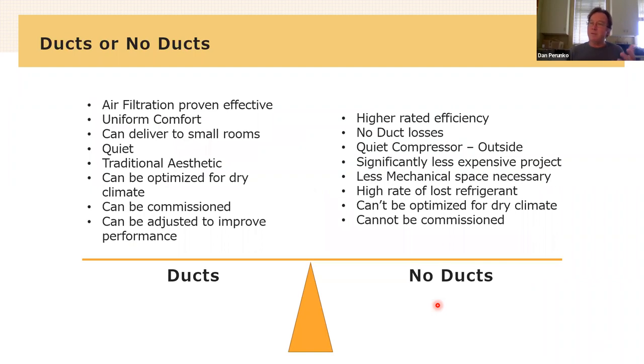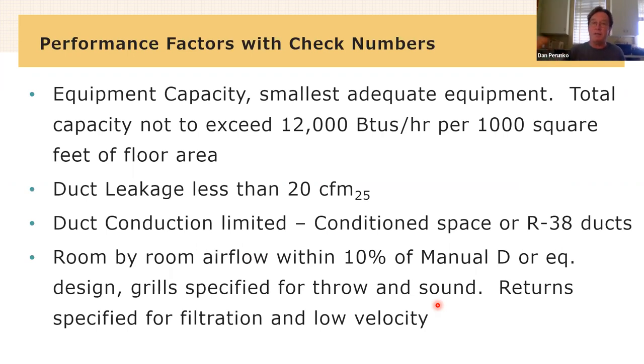And you have to decide whether you're going to do ducted systems or not ducted systems. Ducted systems deal with the entire house effectively, and they're slightly lower efficiency. They also provide air filtration effectively. The non-ducted systems are higher efficiency, super, super quiet. Actually, I want to take that back. Both of those systems can be extremely quiet if they're installed well. The non-ducted system primarily is really high efficiency, generally lower install cost, but lacks the air filtration and the ability to deal with lots of different rooms.